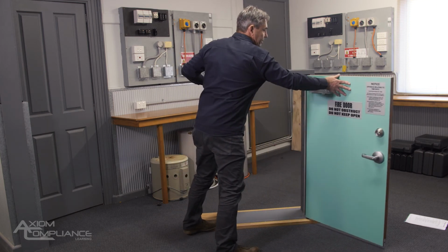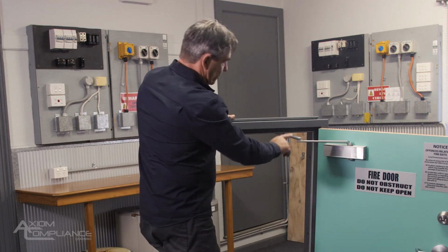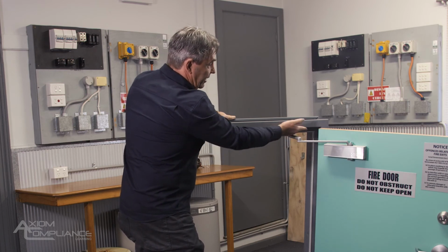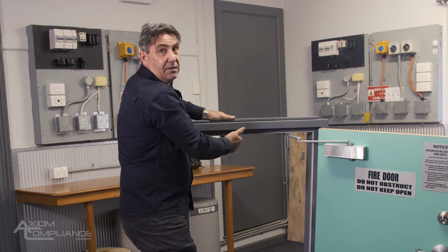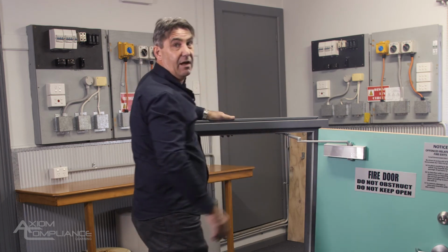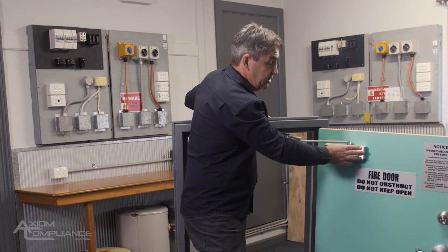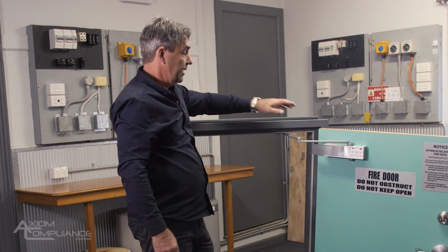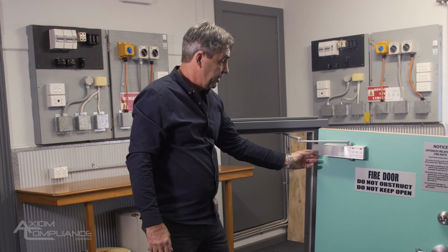So coming back to our door closer, I've got to make sure that the door closer is not obstructed by anything. Sometimes it can get a little bit close to the door frame there. So I want to make sure it's not rubbing on the door frame as it's closing, and that we don't have any leaks, because this has oil in it. It's a hydraulic door closer. There's no leaks. It's pretty much brand new.